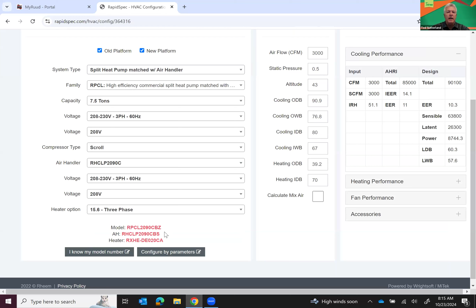Now, in the next column over, you have your inputs for your airflow, static pressure, altitude, cooling outdoor dry bulb, outdoor wet bulb, indoor dry bulb, and indoor wet bulb. Now, most of this you're going to leave the same. On a commercial job, if you're speccing from a print, all of this information should be on your blueprint. So you need to make sure you update this information with what's on the blueprint, because it will affect our cooling performance.